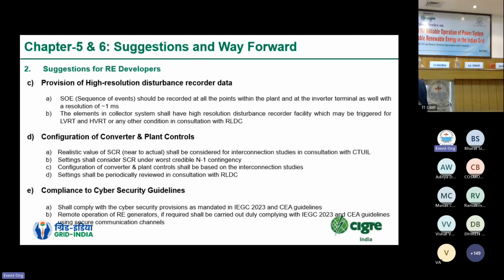Suggestions for RE developers: during the post-facto analysis phase, it is found that high resolution disturbance recorder data is not available with the RE plants. So we request, and we found in the report, that all the RE plants should have a provision to install equipment which can capture disturbance records with a resolution of around 1 millisecond. So this is also one of the important points.